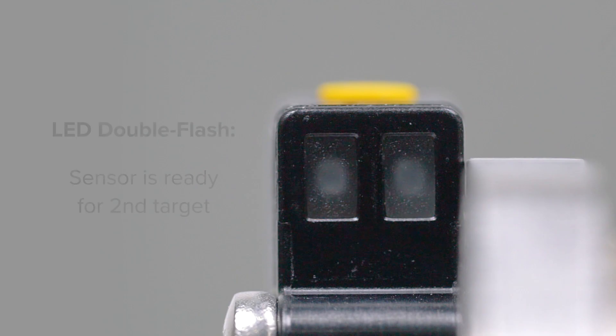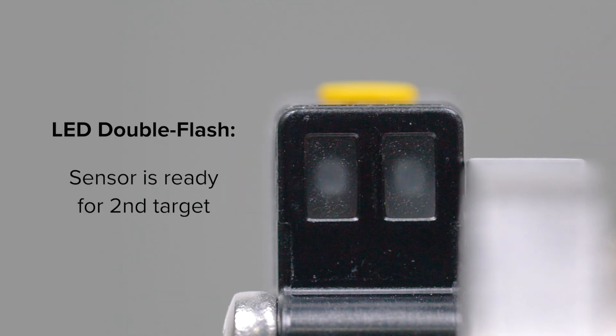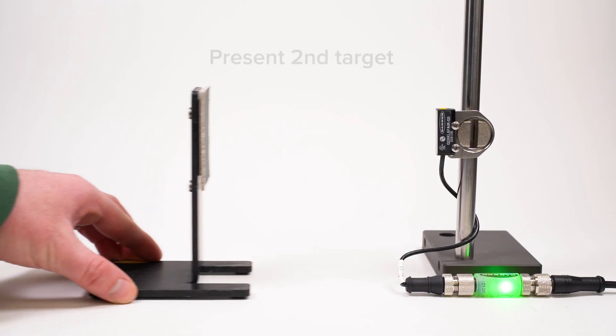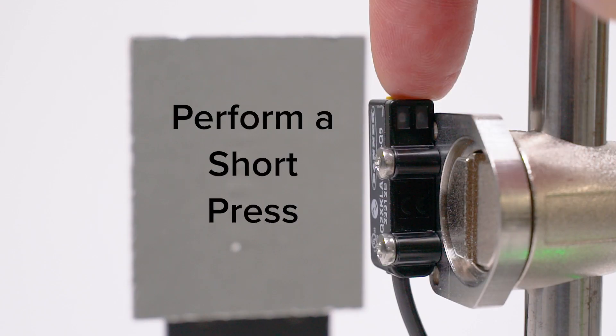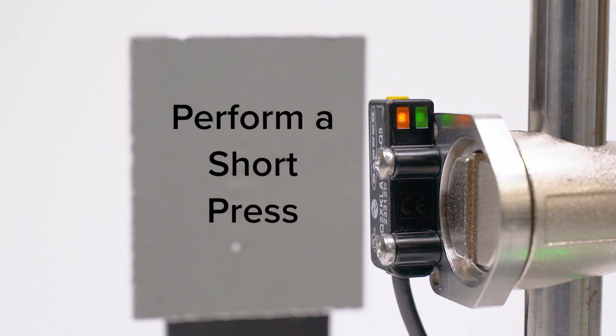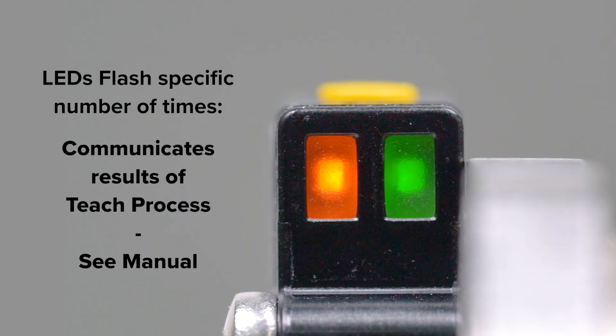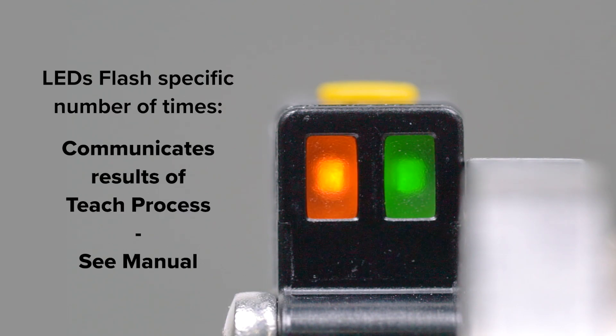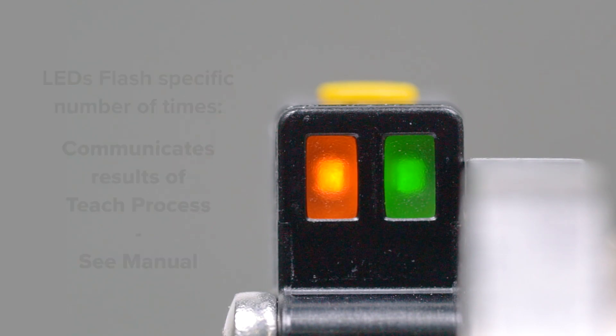The LEDs will start double flashing to indicate that it is ready for the second condition. Present the second target or distance and perform another short press. The LEDs will flash a specific number of times to communicate the result of the teach process based on the table provided in the manual.